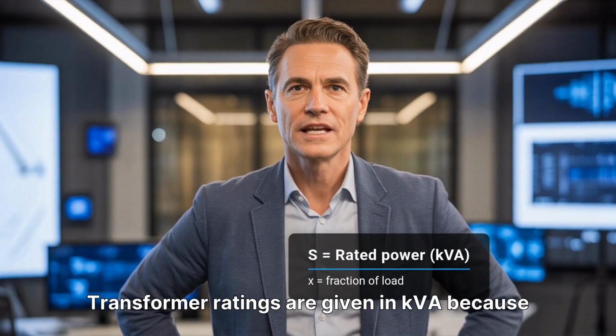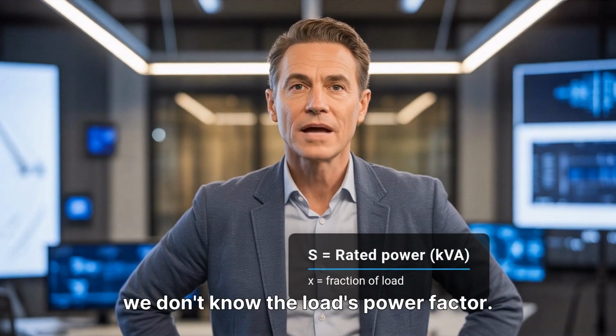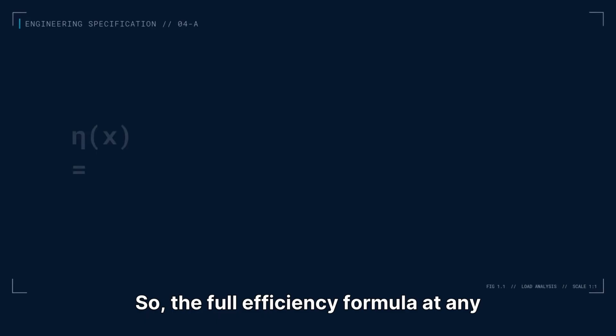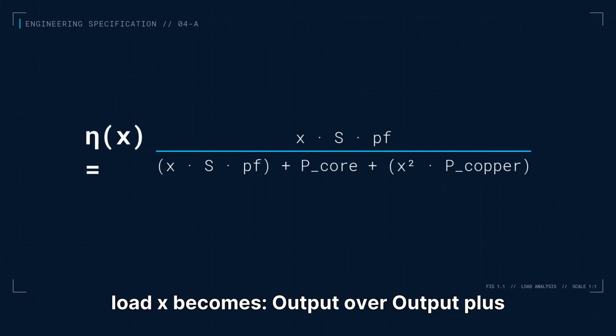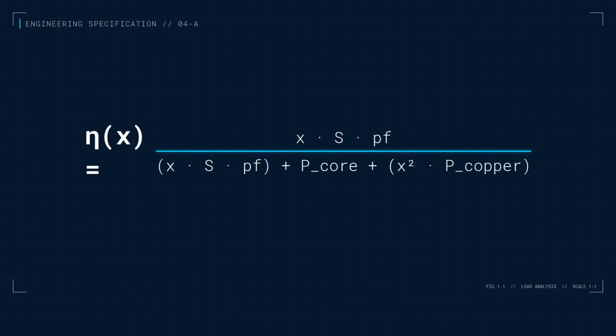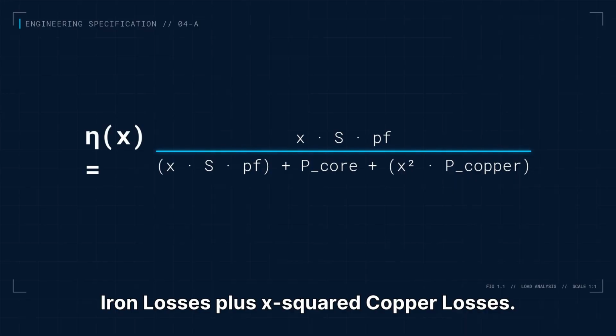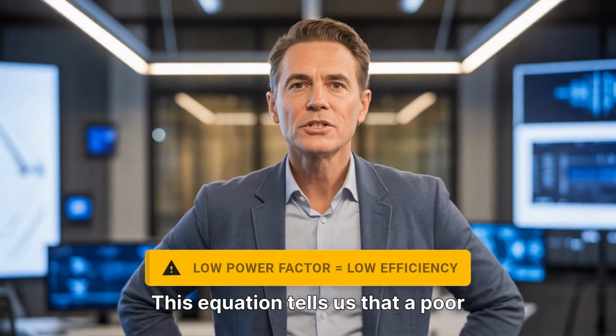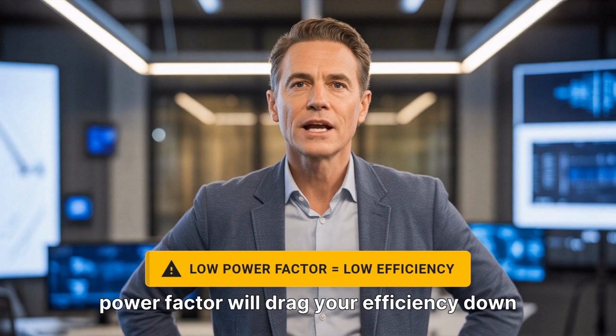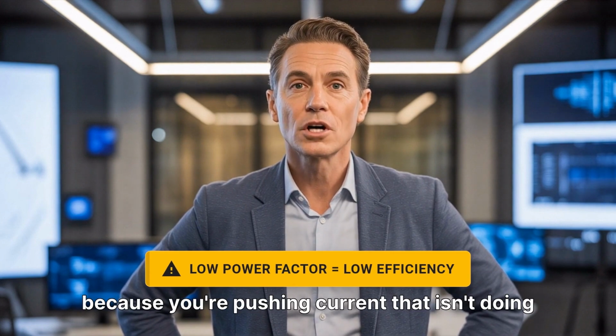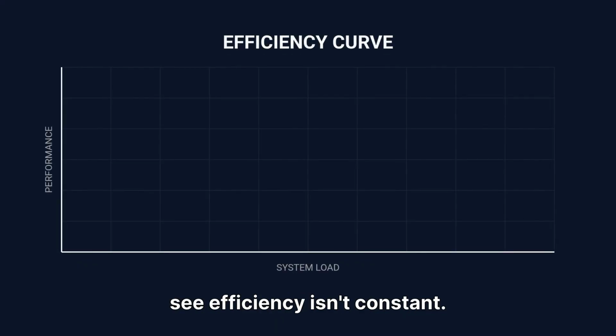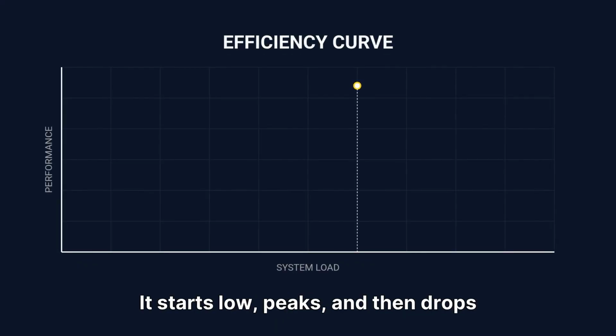Let's put this into a formal equation. Transformer ratings are given in kVA because we don't know the load's power factor. So the full efficiency formula at any load X becomes output over output plus iron losses plus X squared copper losses. This equation tells us that a poor power factor will drag your efficiency down because you're pushing current that isn't doing real work. If you look at this graph, you see efficiency isn't constant. It starts low, peaks, and then drops as copper losses take over.